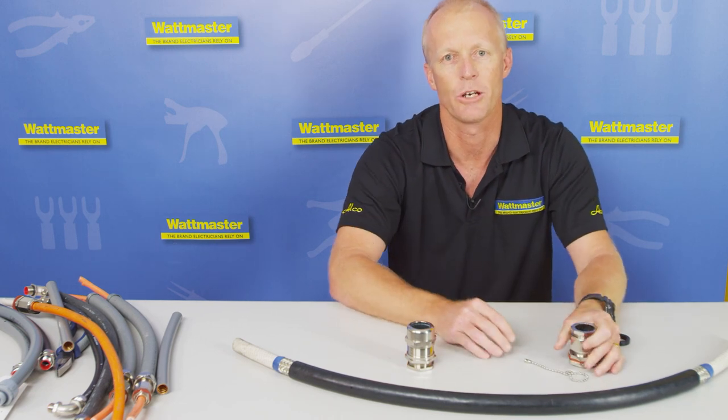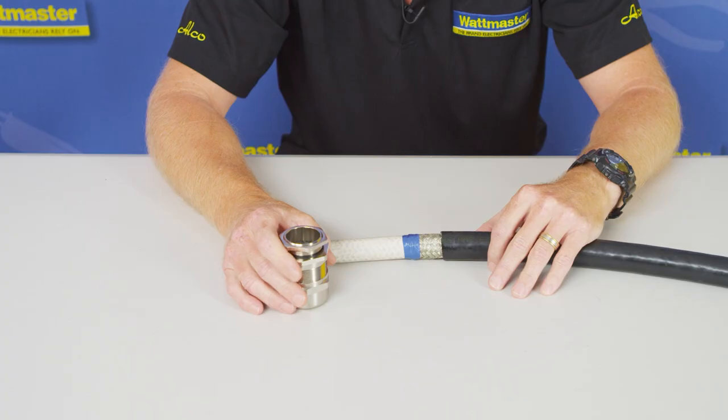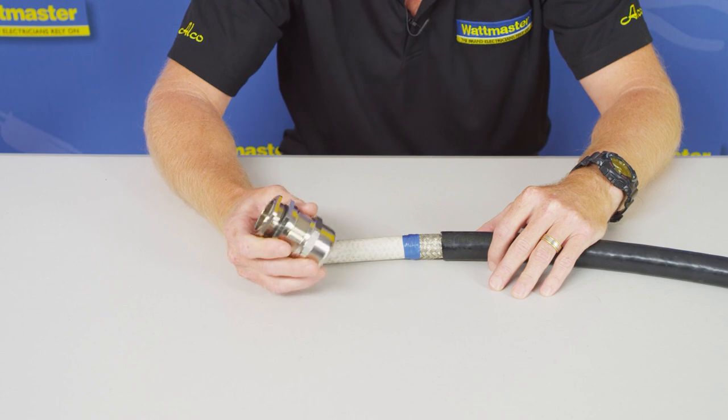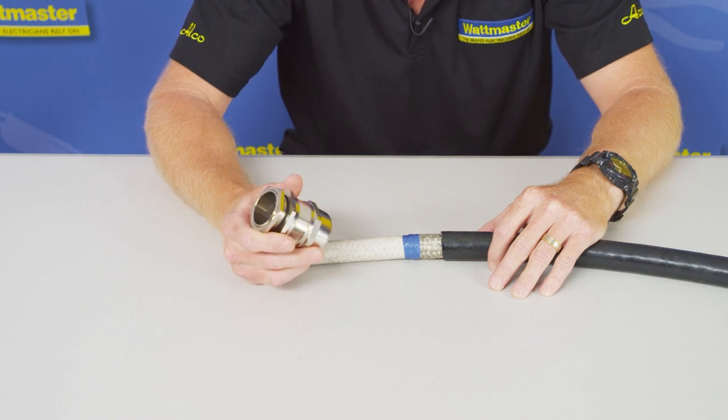This can terminate both the braided and the taped cable. When terminating the VSD cable, the whole point of the procedure is to get good 360 degree contact onto the braid.